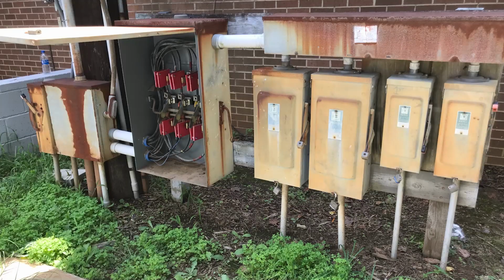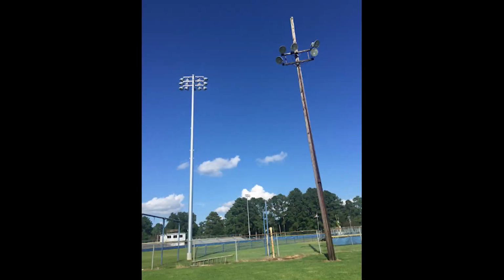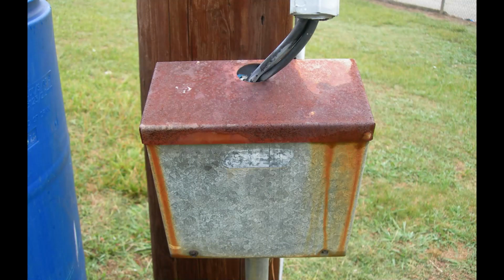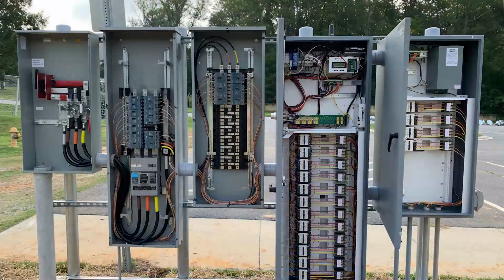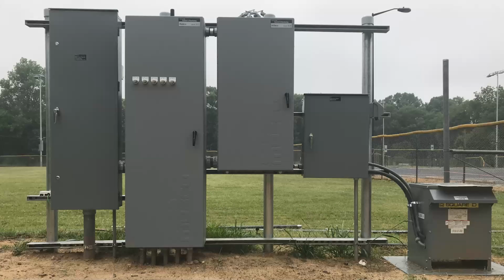Inspecting your facility service entrance, poles, and distribution boxes is critical because these are where some of the most potential hazardous safety issues can arise. Moving on to your electrical service, which includes metering, your electrical panel or panels, and your lighting controls. When you inspect your electrical service, you want to make sure that all covers are in place and that it is secure from unauthorized personnel. Also, make sure that all labels are properly installed.